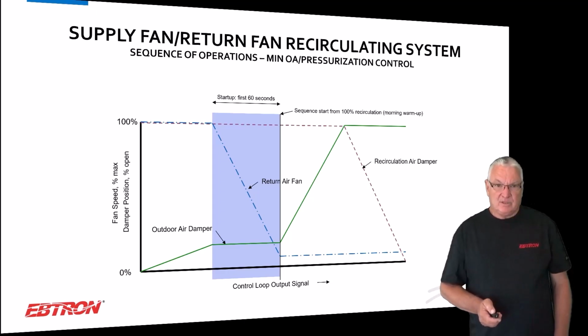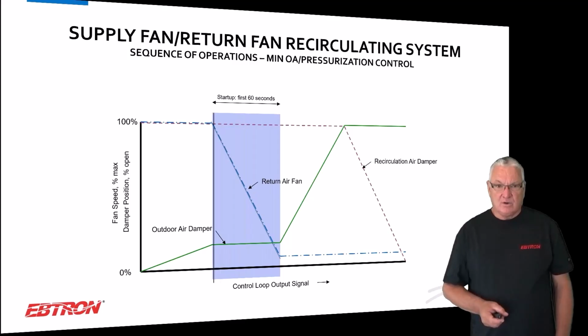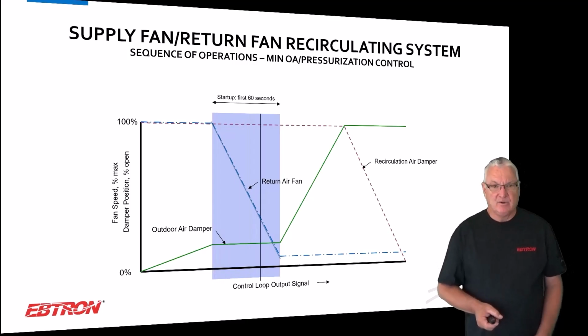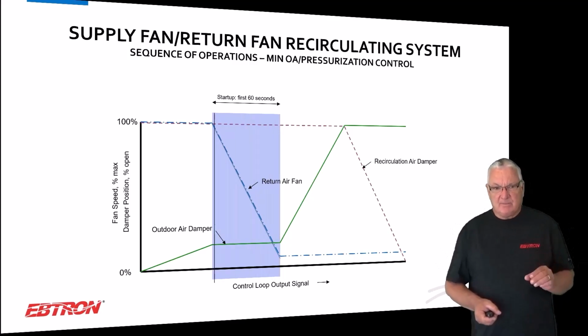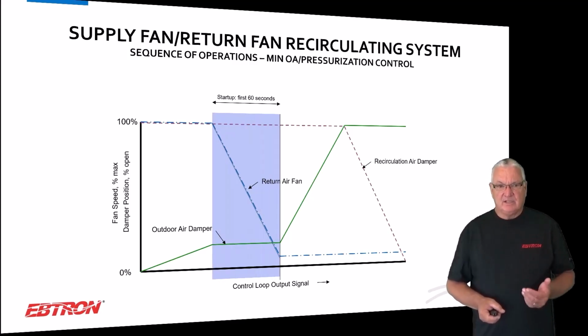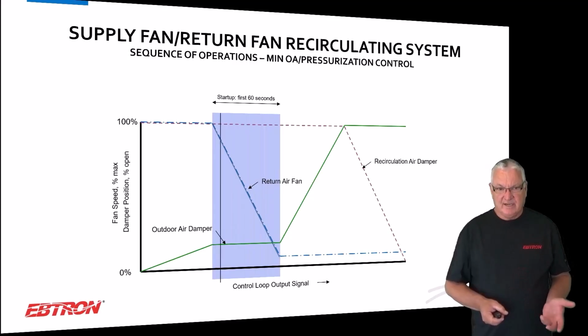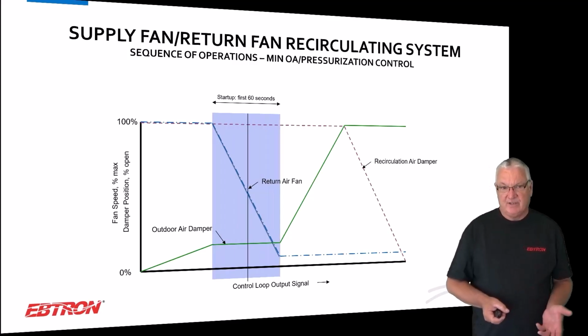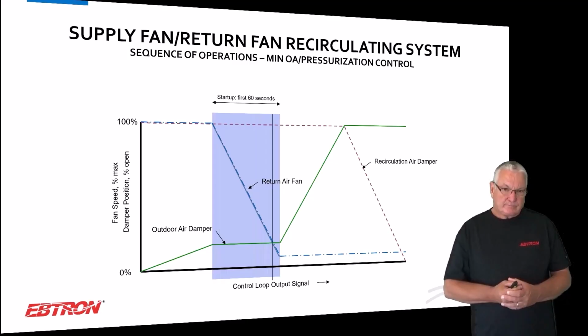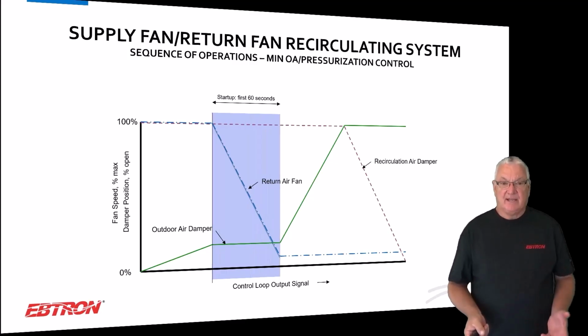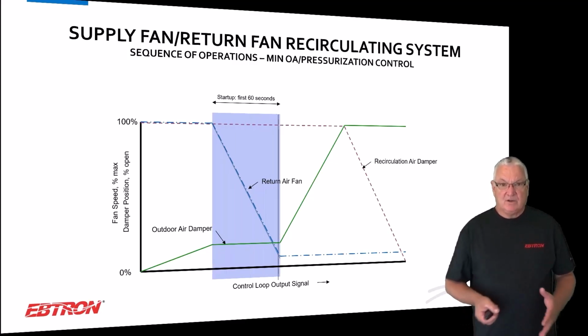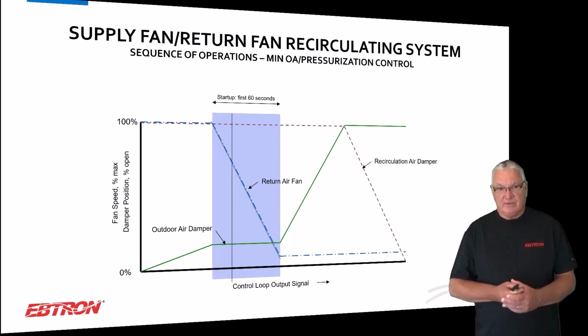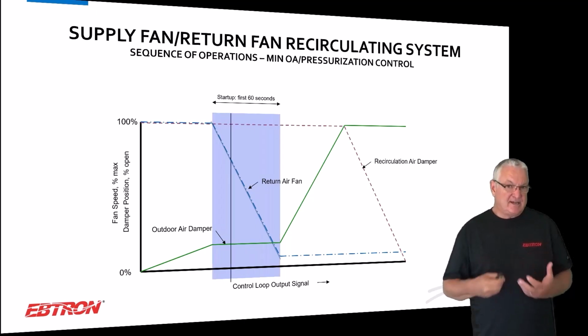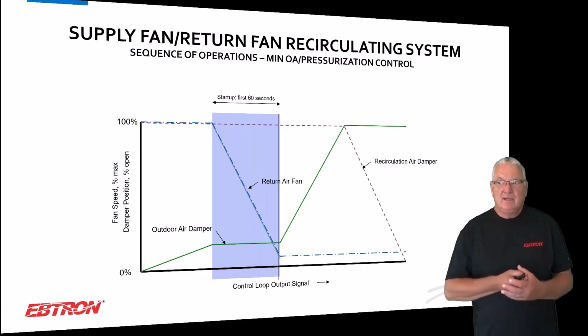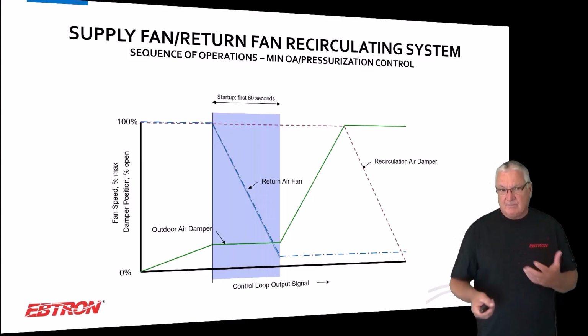And the way our sequence is going to work is, I'm coming on a night setback here. So as we're coming from the outside air damper being fully closed on the total left side of the screen, it's going to go to this minimum position that we've determined. Basically it takes time for the damper to get there, so we limit the sequence to only operate in this area that I'm showing you, okay? That means the only thing that's actually modulating is the return air fan, until we get our minimum position.